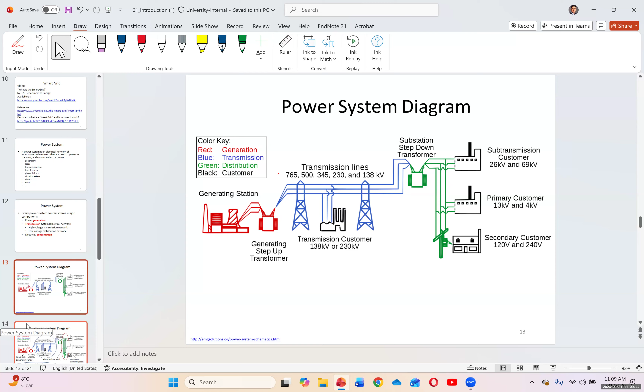We have different systems in different parts of the country, and different countries have different standards as well. The transmission customer is at 138 kilovolt or 230 kilovolt. Then at a city, for example, we have the substation step-down transformer that reduces that voltage for sub-transmission customers, around 26 to 69 kilovolt, or for primary customers, 13 kilovolt and 4 kilovolt, or secondary customers, which are homes, at 120 volt or 240 volt two-phase that you use in your dryers and ovens or electric cooktop.